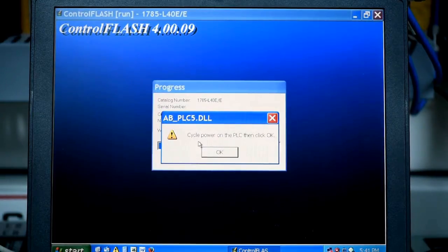Okay, we're now at the point, after that flash, when you go to the manual, we are at step 3, G as in George. Now, since we're going from Series A to Series F, we have to replace the PROM in the communication port on the communication card. It's either U7 or U12 if applicable.